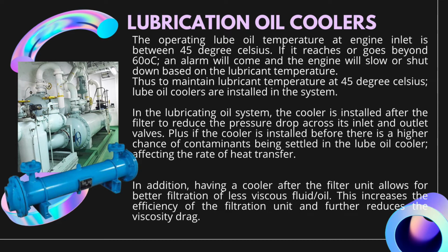Lubrication oil coolers. The operating lube oil temperature at engine inlet is around 45 degrees Celsius. If it reaches or goes beyond 60 degrees Celsius, an alarm will come and the engine will slow or shut down based on the lubricant temperature. The cooler installed after the filter is to reduce the pressure drop across its inlet and outlet valves.